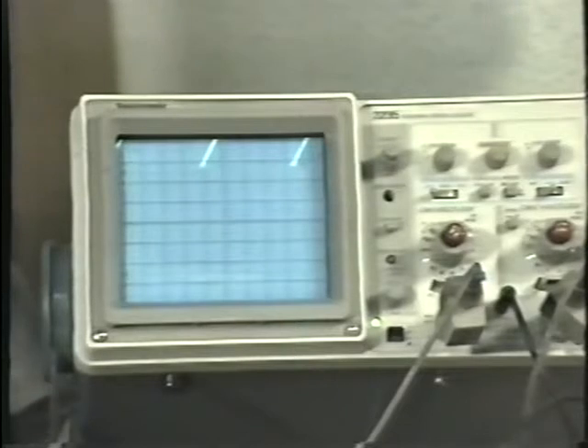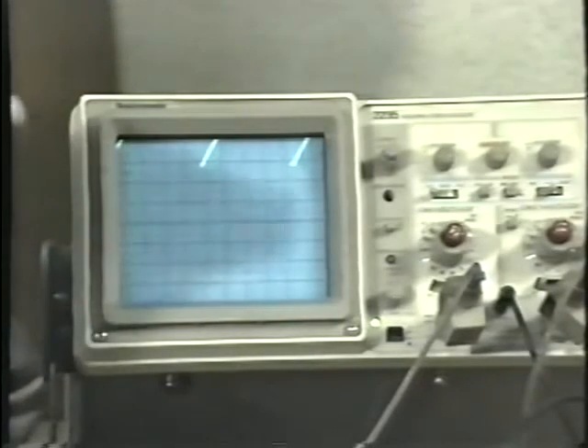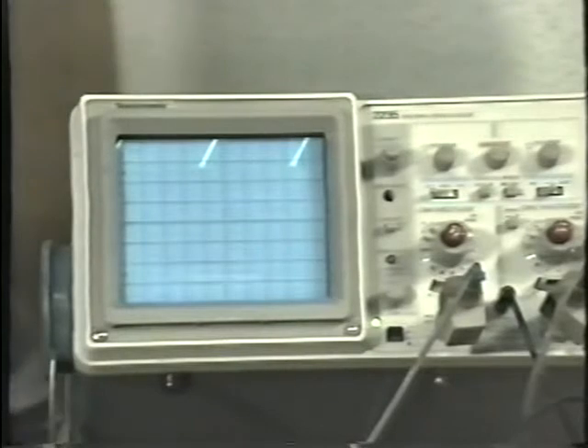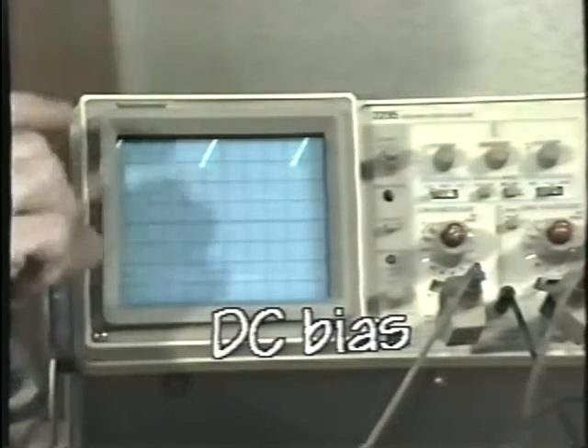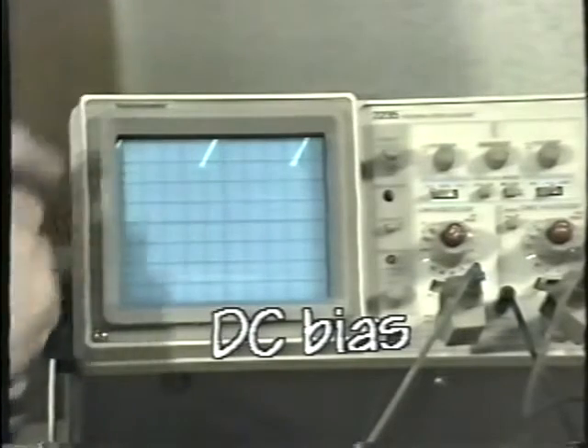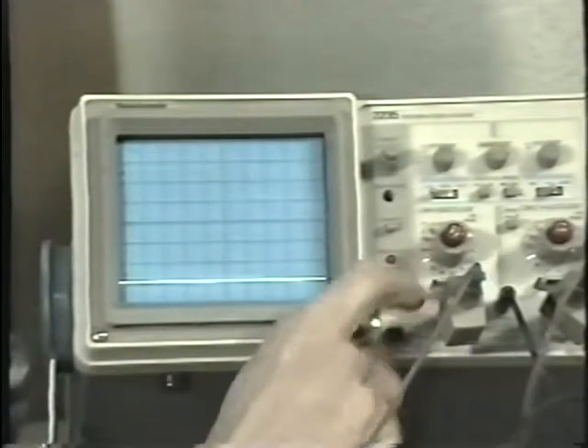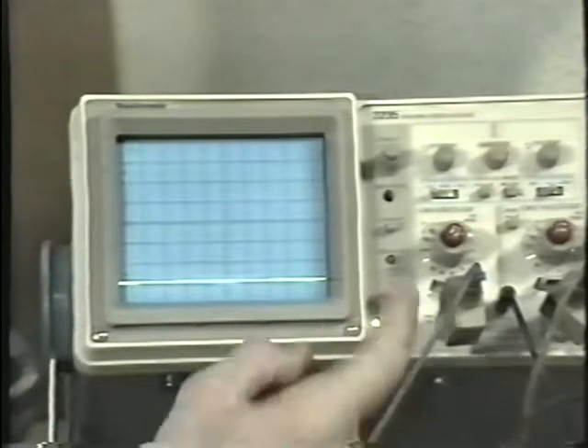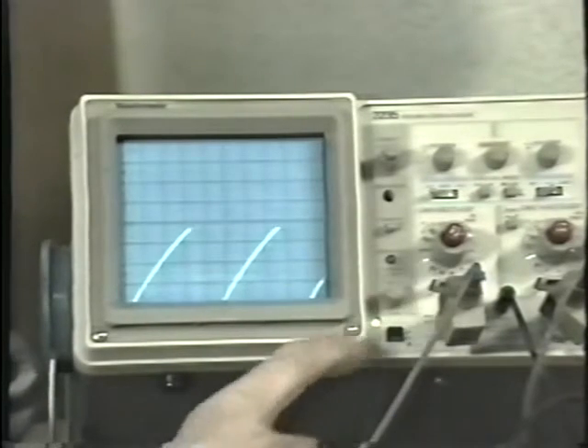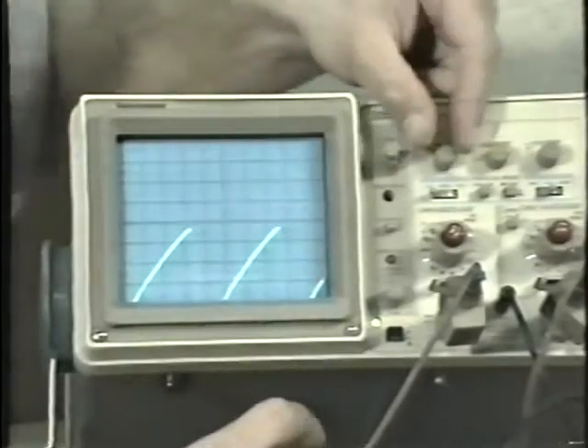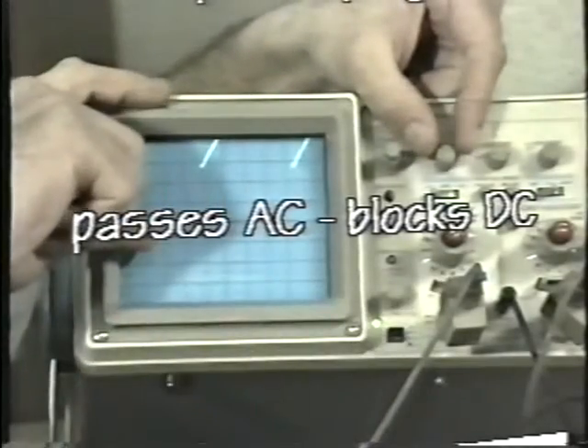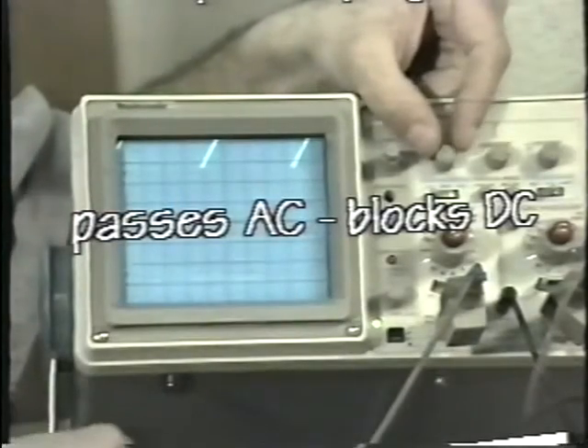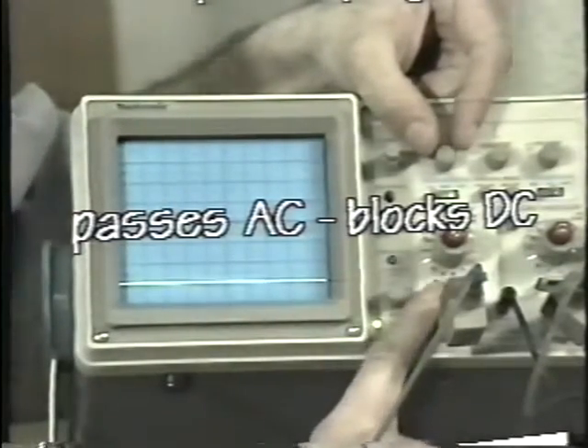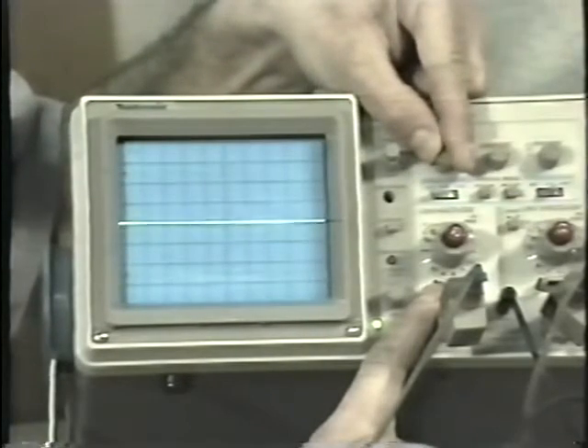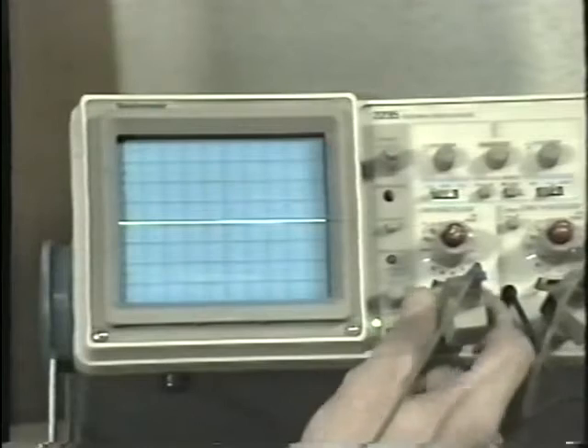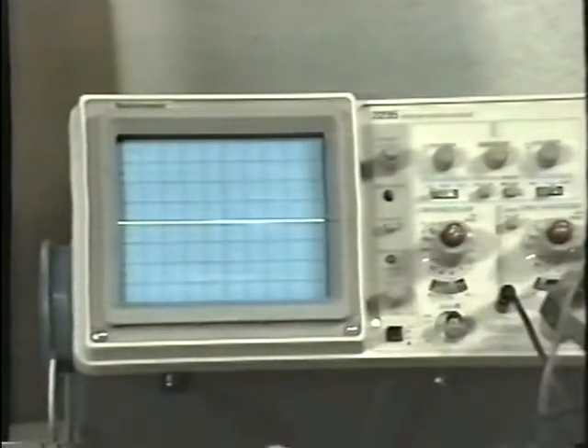But it is not at all uncommon to have some type of a signal riding on top of what we call a DC bias. To eliminate that DC bias so that we can see the signal, you can flip the input select control to AC. And what that will do is, if there's any DC on the signal, it completely removes that. It completely ignores that, so that you can set the input to ground, set your baseline in the center, then flip the input select, and let me remove the probe just so you can see what it looks like.